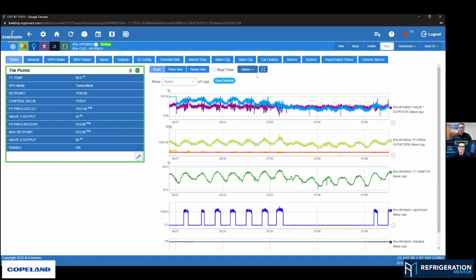So there's an important control factor of that where we're looking at the drop leg temperature. So the outlet of the gas cooler or condenser, and trying to create subcooling. So what we're looking at there was temperature from that drop leg, trying to maintain a set point, which typical across most of the OEMs is around 5 degrees of subcooling. There's a couple of them that are a little lower and a couple of them that go a little higher as well. And sometimes dependent on the mode the system's operating in. But in essence, it's just one set point, trying to create subcooling.